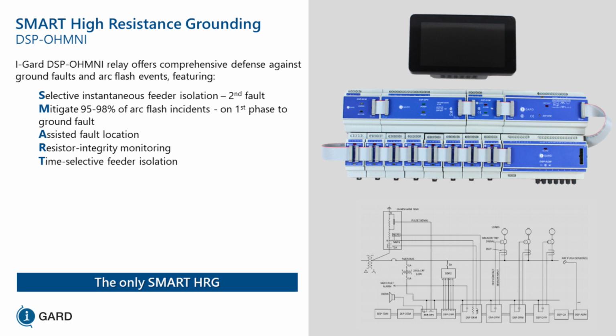Again, the threat of having an ungrounded system was if you had one fault on the system, you can't find it. But if you have a second fault on the system, then you have a phase-to-phase fault, phase-to-ground-to-phase fault. Something has to trip. It may be one feeder, maybe the other feeder. It could be the main breaker, but something has to trip. With a smart HRG system, we give you second fault protection, which basically means in a critical process, you can determine between two feeders which one has higher priority. And the one with the lower priority will trip, keeping your critical processes running at all times.